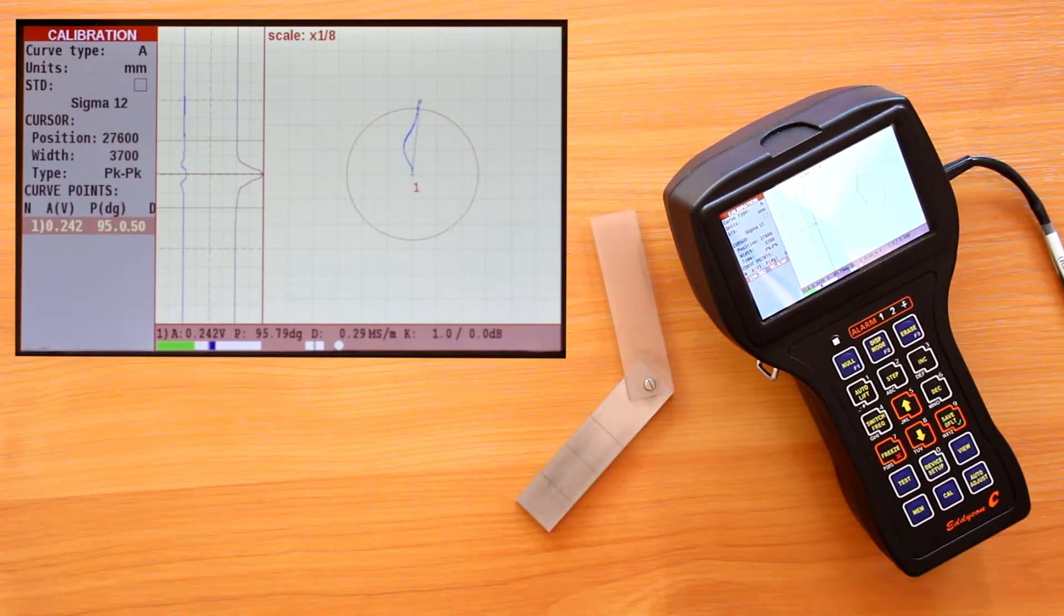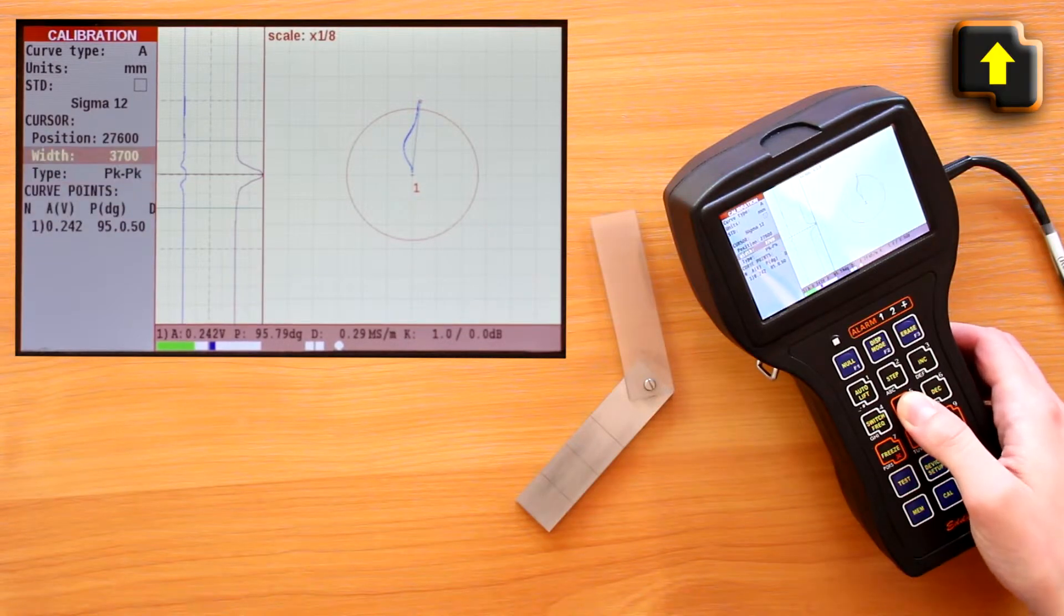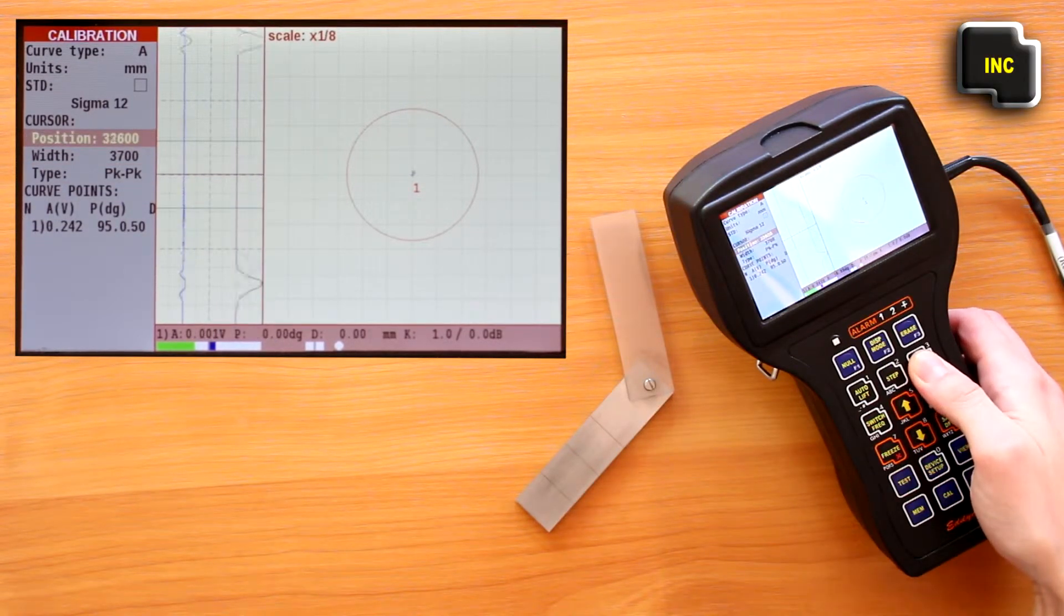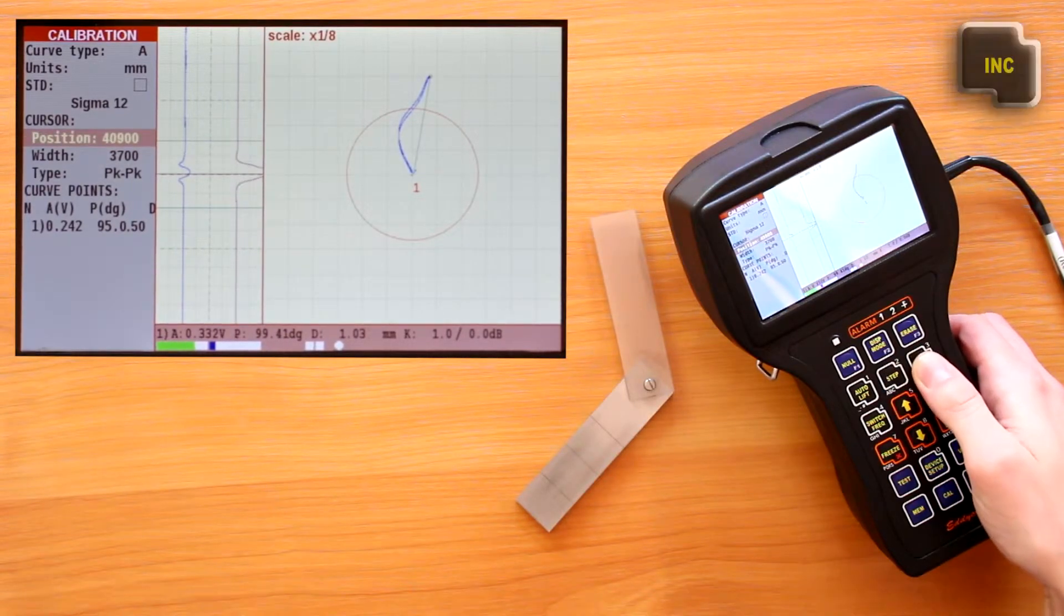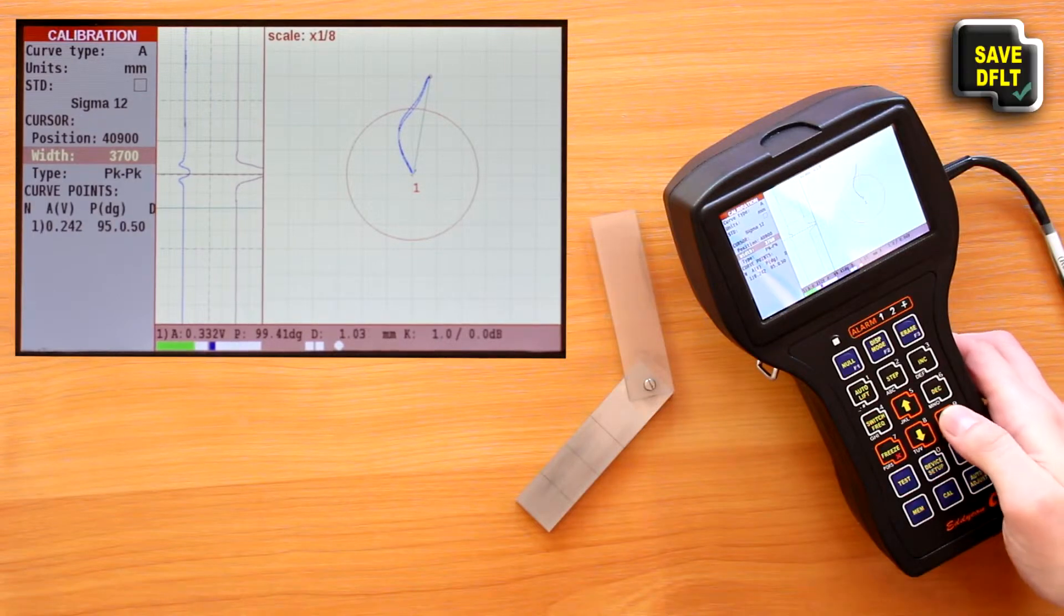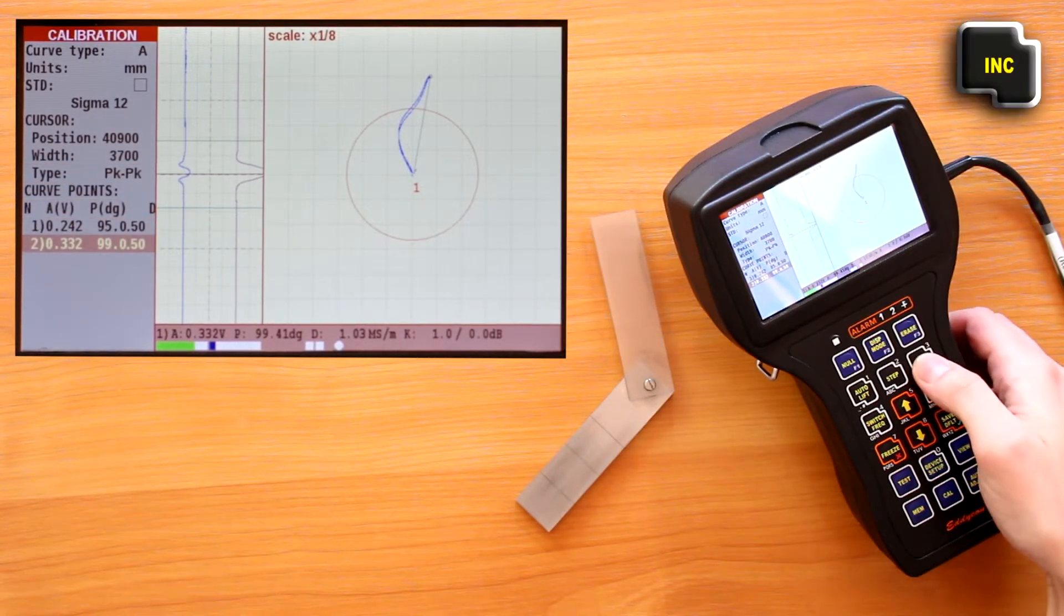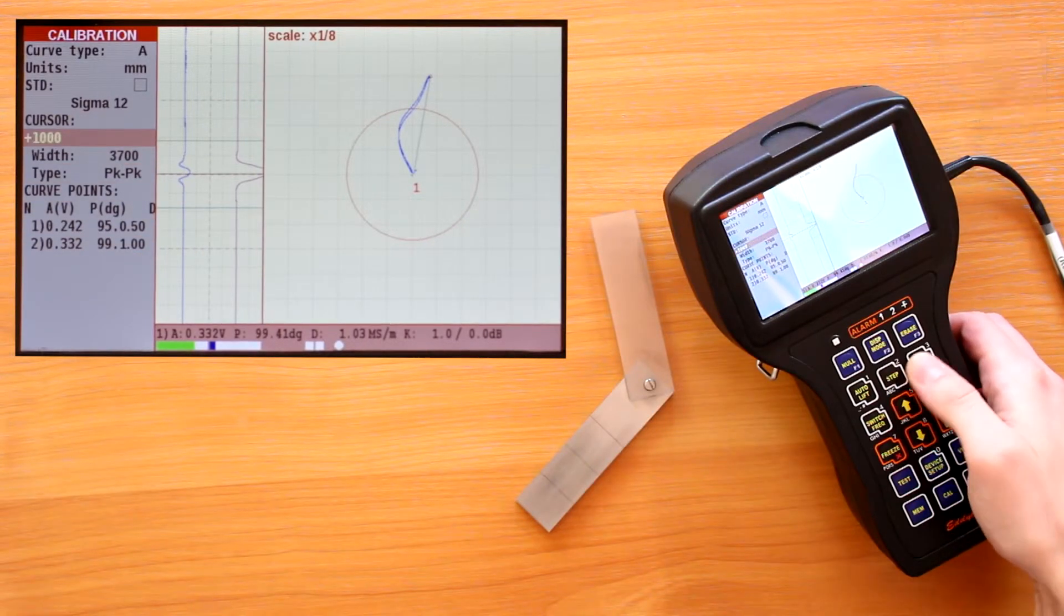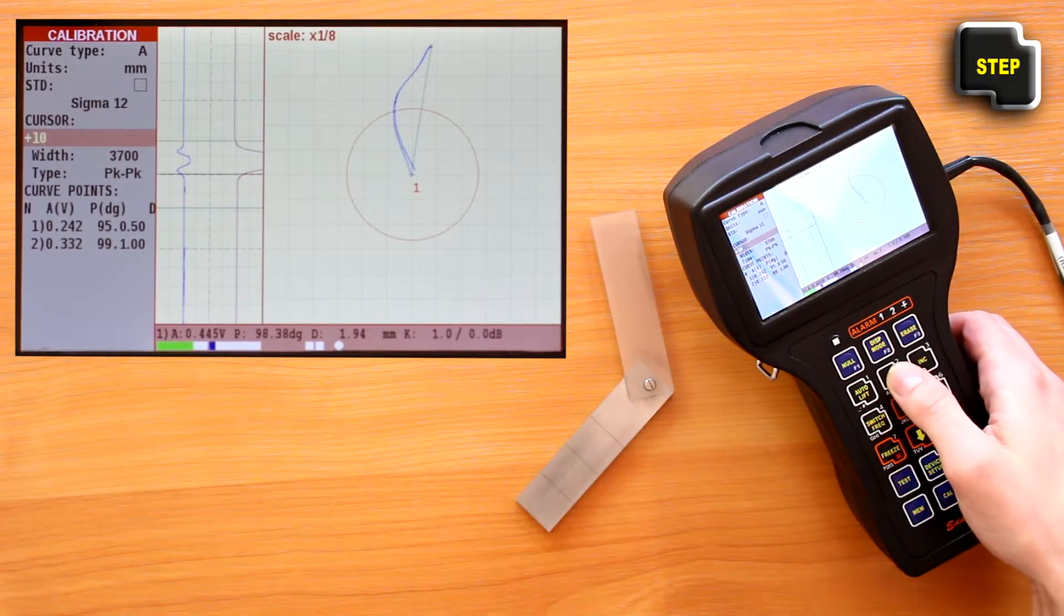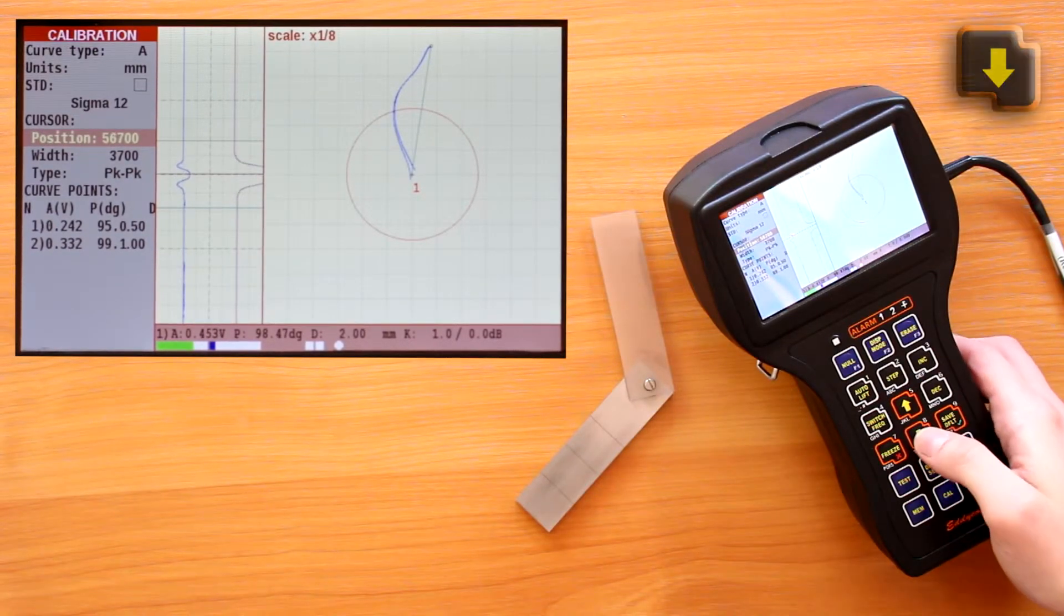Then perform similar operations for all other defects. Each newly added point of the calibration curve is assigned with a number—one, two, three, and so on. The max number of calibration curve points is 16.